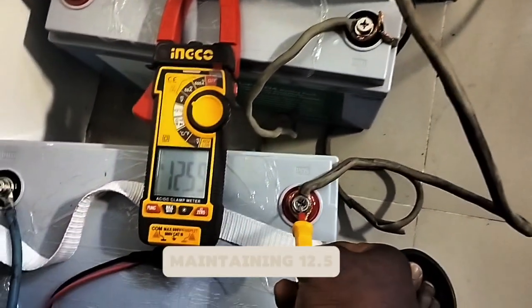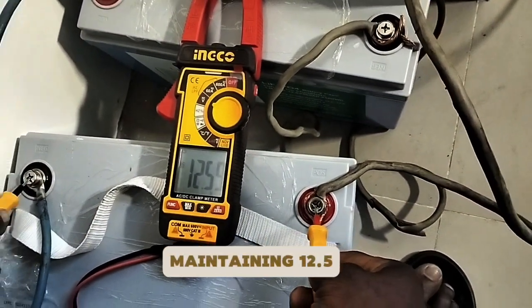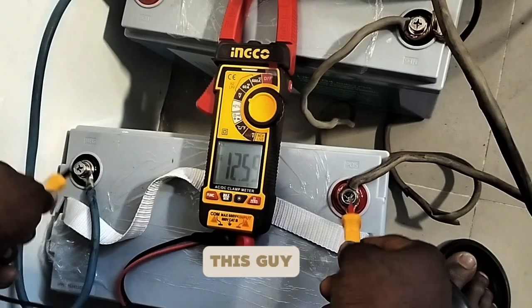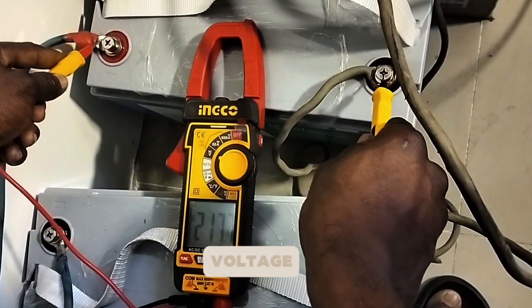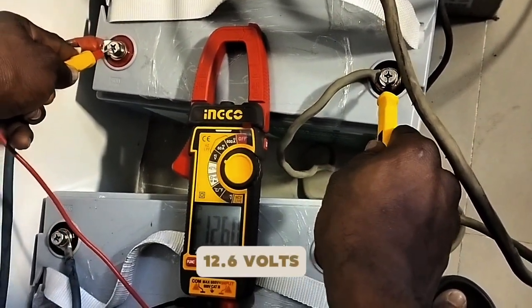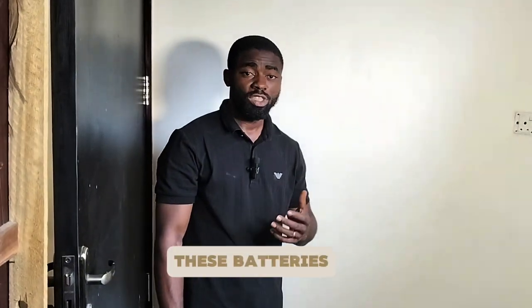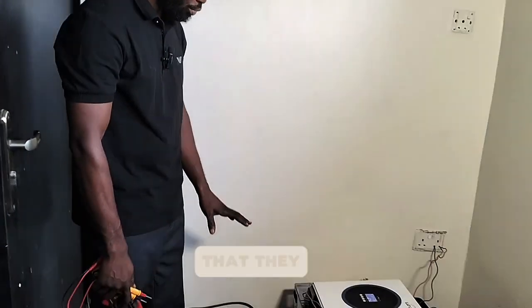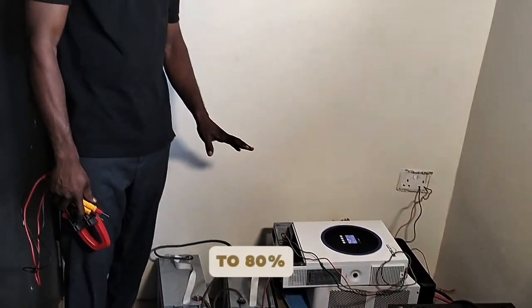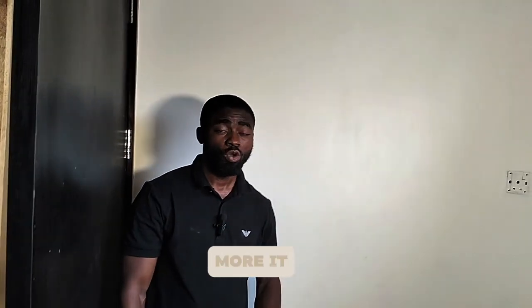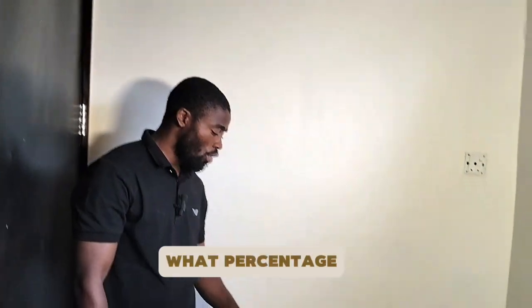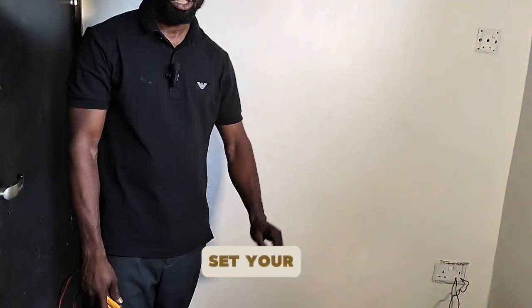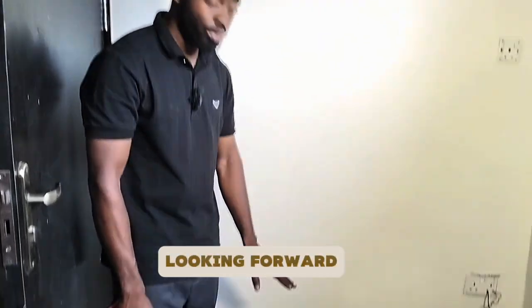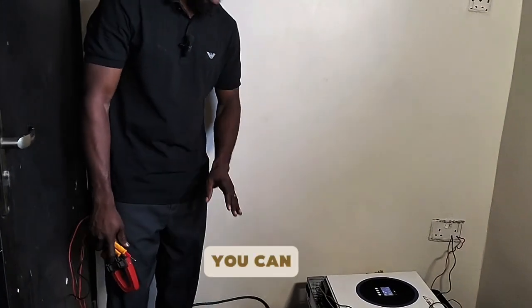This battery is still maintaining 12.5 volts. This guy also might be maintaining the same voltage, 12.6 volts. From our load test, these batteries have actually proven that they can give us up to 80% depth of discharge or even more. It depends on what percentage or what depth of discharge you set your battery to. For those of you that are looking forward to do a 1 kVA system, you can go for this battery.